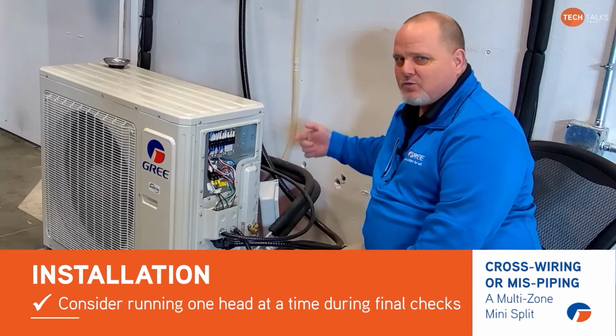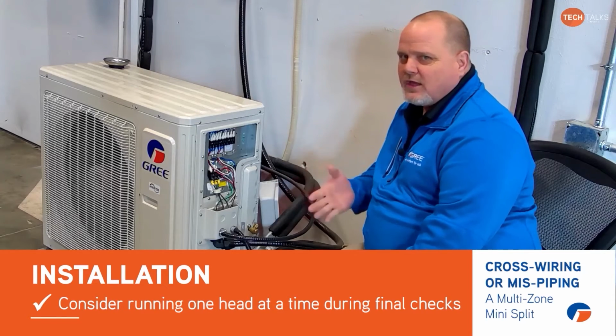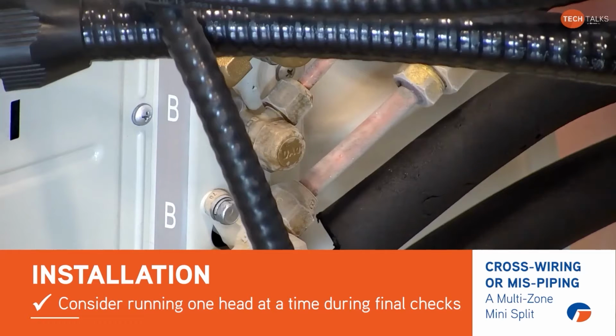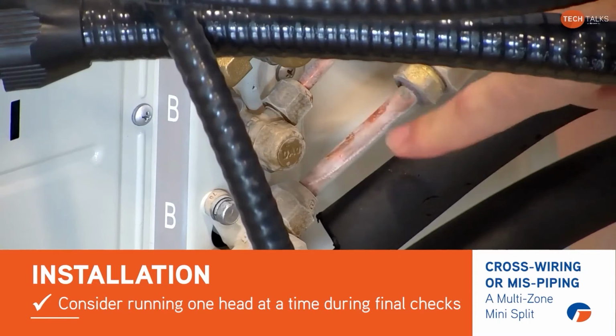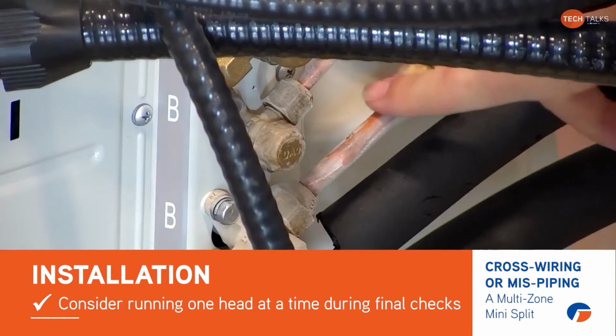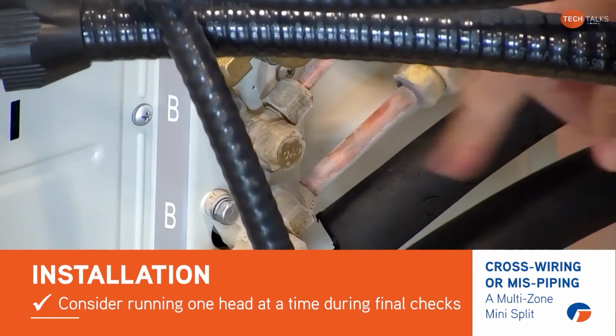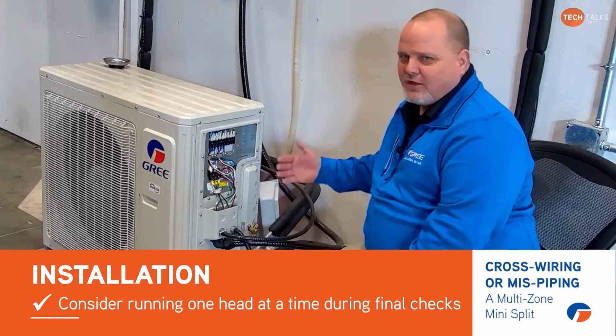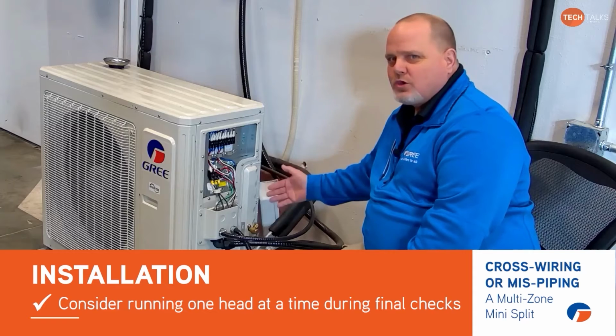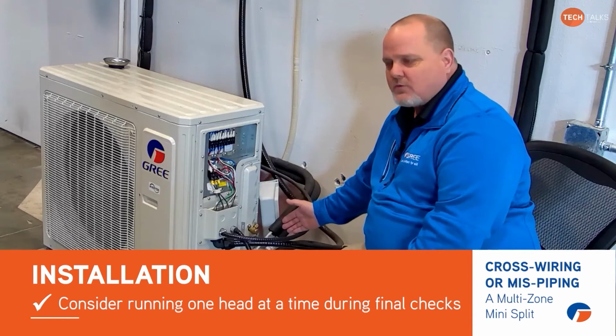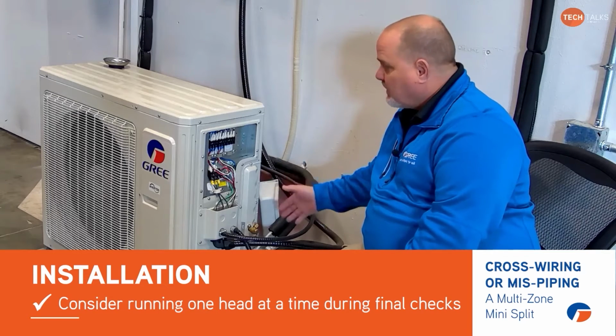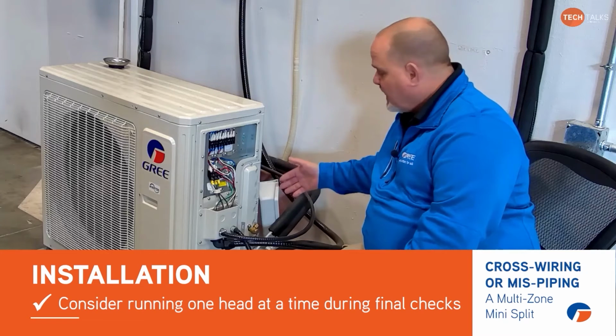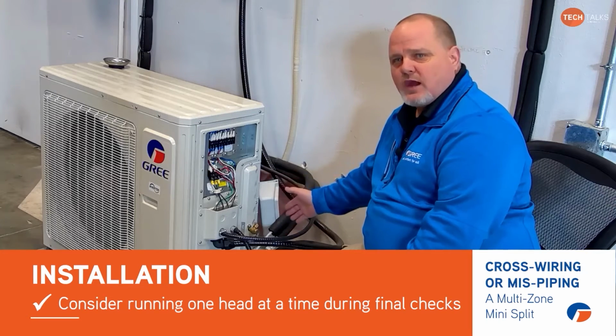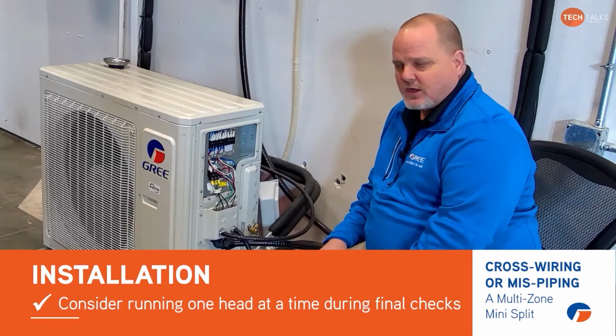We never ran just one head, so then you leave thinking the whole system's working properly, and then the next day or two the homeowner's calling you saying, hey, this thing's freezing up. And then you go out there and you turn all of the units on again and nothing freezes up. Well, it won't do it unless one head is calling. So be very careful of that. And you may want to do your final checks running one head at a time and make sure you got proper pressures and the unit's not freezing up.